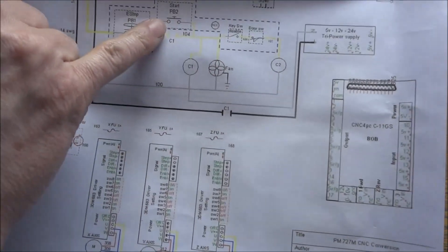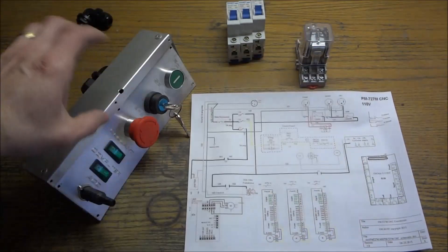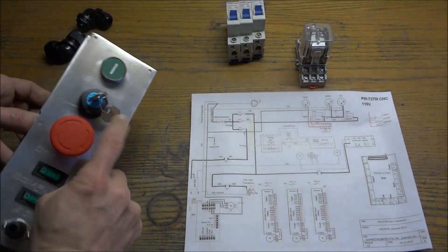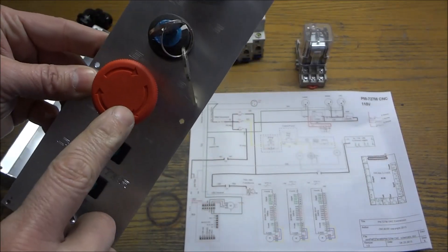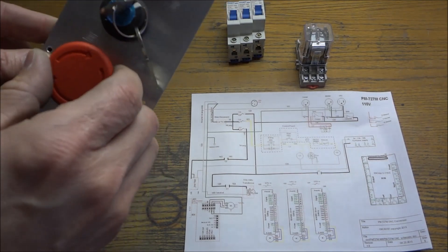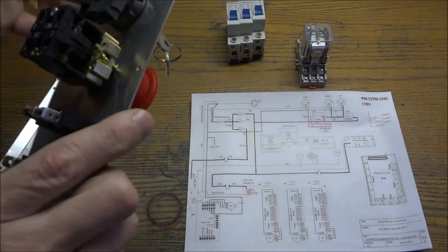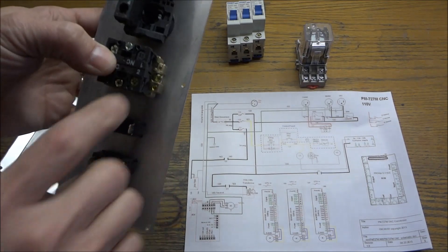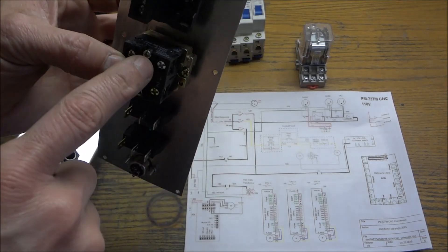And also one set of contacts that is our holding circuit that keeps everything energized once you let go of the momentary push button start. I had to order my start button which came in, or my power on button, and I also changed out my e-stop. I didn't like the one I had so I ordered a different one. It has the same type contacts as the start button. The start button of course is normally open and the e-stop is normally closed. You will need two sets of normally closed contacts on the e-stop.